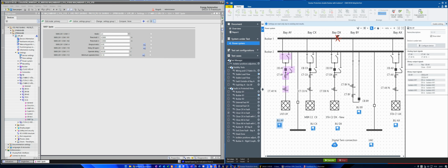And why is this important? This is important for a kind of fault that I will show here, the famous blind spot, or end fault protection. That is a fault that you can have between the circuit breaker and the CT. And for example, what happens in this case?